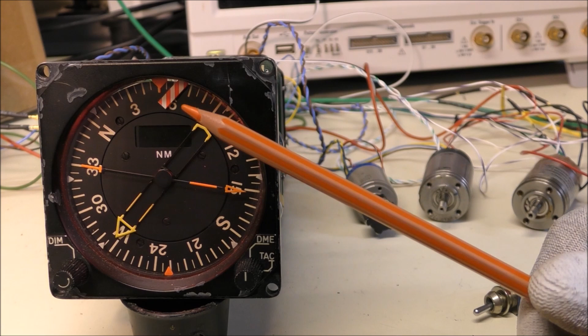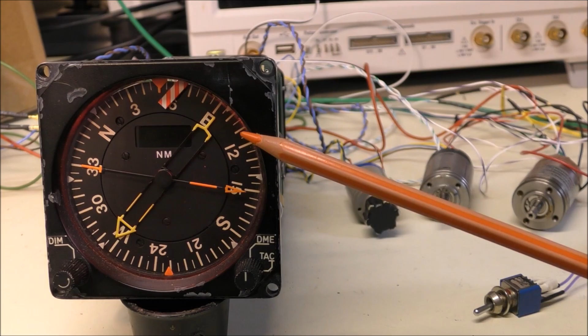There is also the flag here. In order to activate the flag, we need 3 conditions. The first is the presence of an AC voltage for the reference winding of the AC motor. The second is a small error voltage on the control transformer. The third is the presence of a 28 volts DC voltage on a particular pin, which indicates that the horizontal gyro works normally. I have simulated this voltage using this switch here.